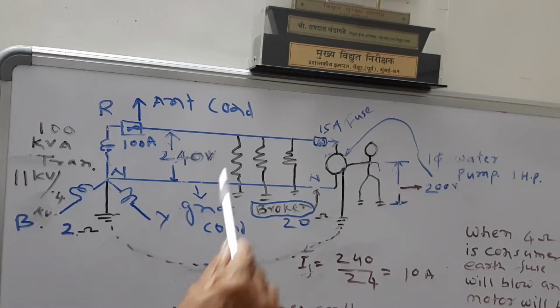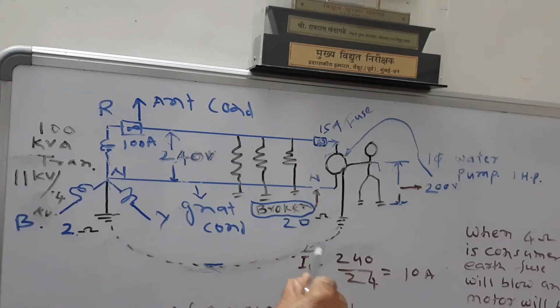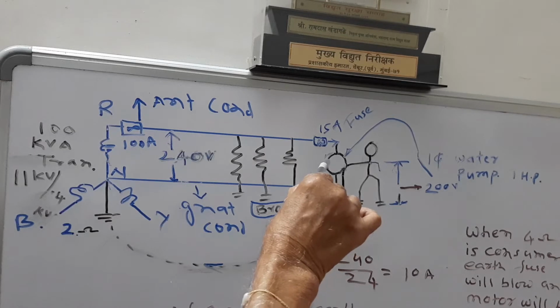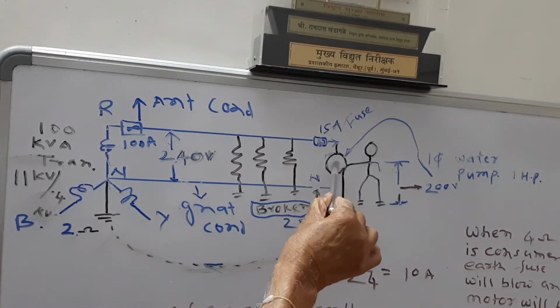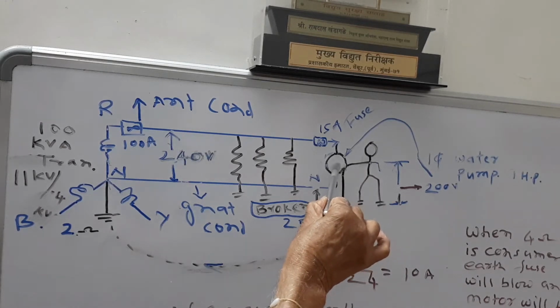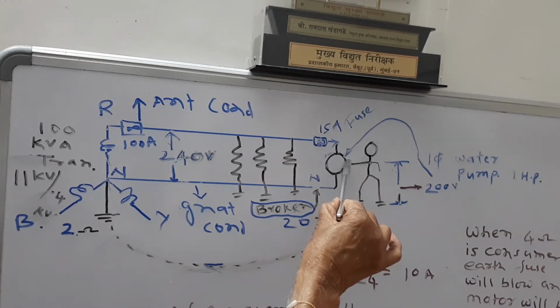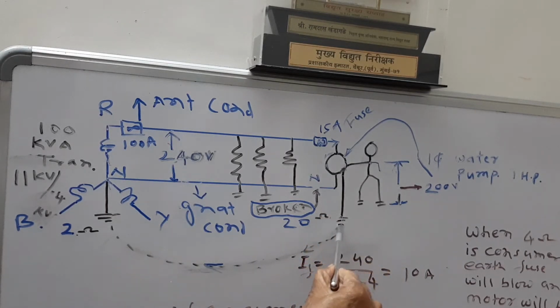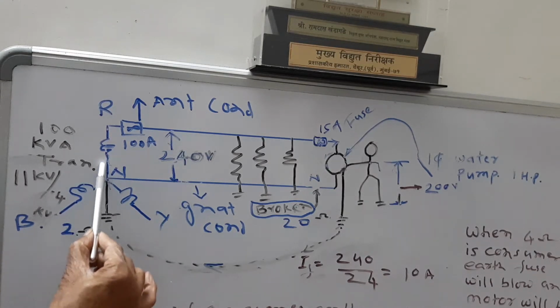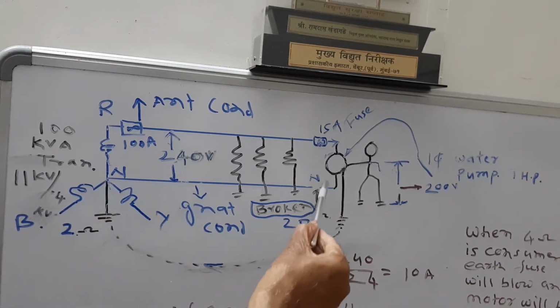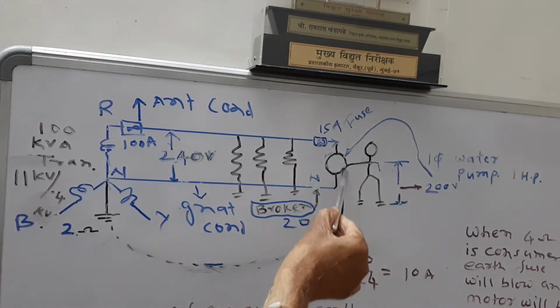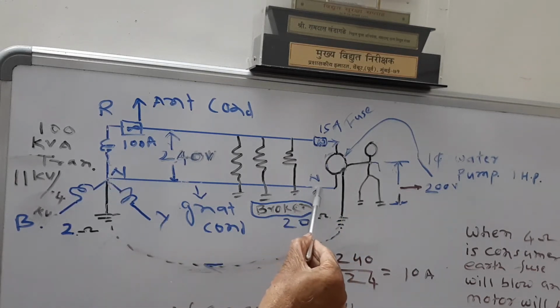Now please see, if we study this complete circuit, we have to first trace the path of the short circuit current. As soon as the coil of this motor fails and the leakage current goes to this frame, this current goes like this into the earthing, like this, like this, like this. This goes into this neutral, and then in this neutral, and then it is circulated like this.